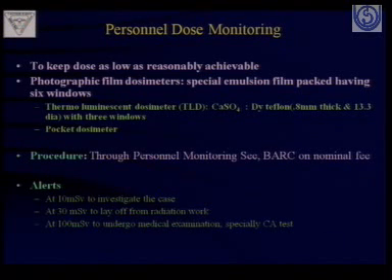Now personnel monitoring is again a very important area which is often neglected by people. People don't wear these TLD badges, they don't keep any records. The radiation workers have to be continuously supervised for this purpose, otherwise we will be faltering on the radiation safety aspect. As we know, 10 millisieverts to 30 millisieverts is an area where the safety requirements have to be monitored. These TLD badges have to be examined quarterly by a person who is qualified in this.